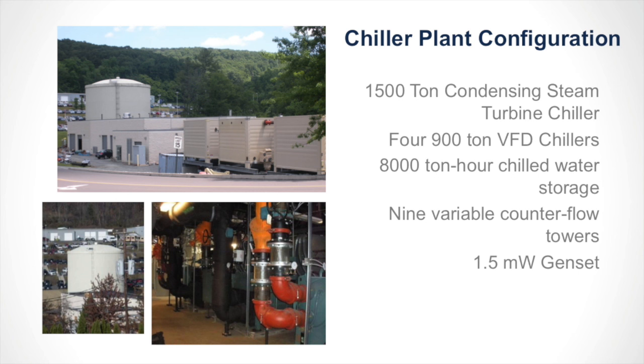We've got, and that tank is 8,000 ton hours, so it's a 1 million gallon tank with a 12 degree delta T, which equates to 8,000 ton hours of cooling and storage.